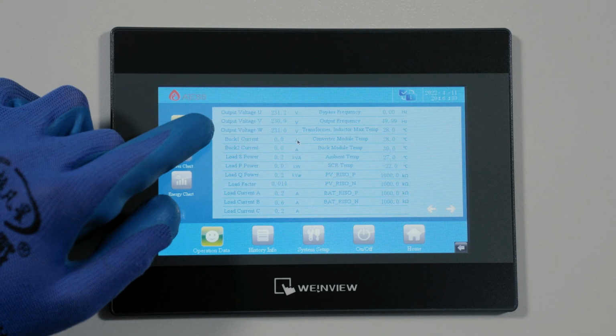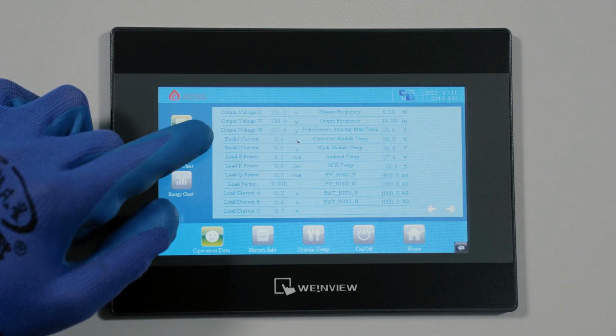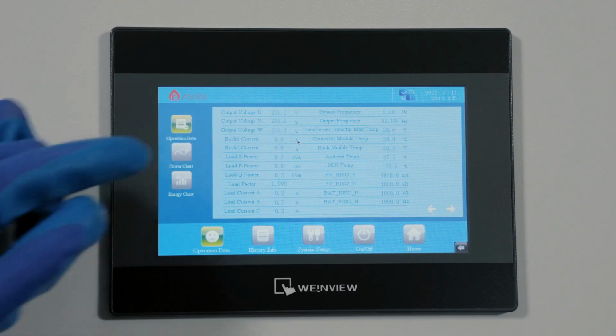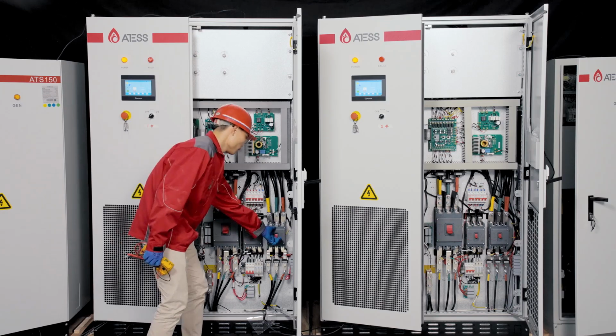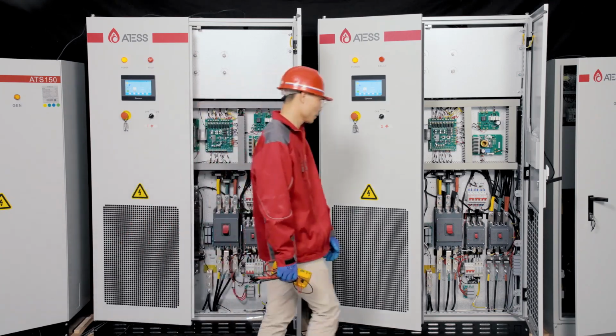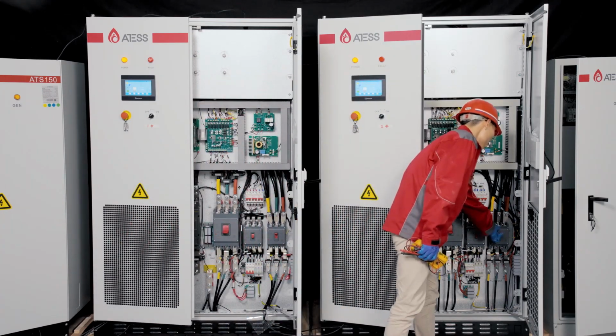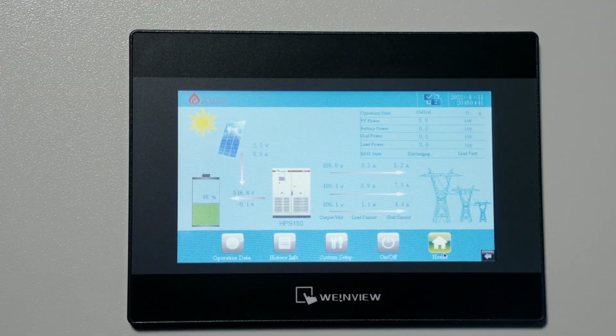Compare the phases voltages in the 2 HPS data pages and check whether the voltage of each phase is different. If there is a large difference, contact our after-sales team. If the voltage difference is not large, close the load breakers of the 2 HPS. Compare the load power of the two HPS. If the power difference is large, please contact our after-sales team.